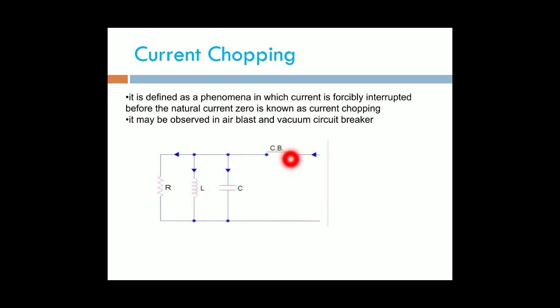This is the circuit breaker, an air blast circuit breaker. We know the shunt reactor also. This is the inductance, the shunt reactor. We know that the shunt reactor also takes magnetizing current. This reactor takes the magnetizing current at every time. This magnetizing current is low under normal conditions. Normal conditions means no fault in the line, so the magnetizing current is low.